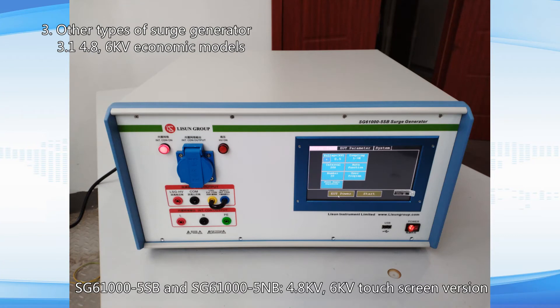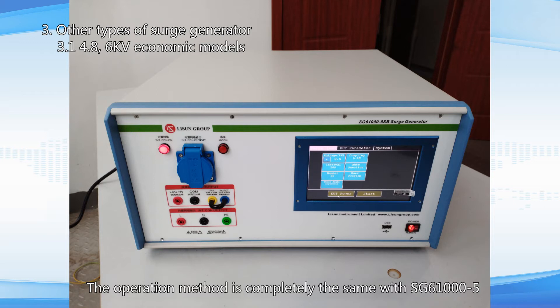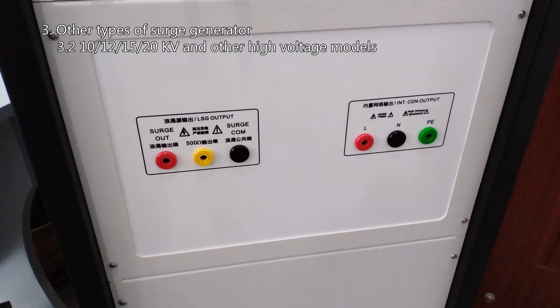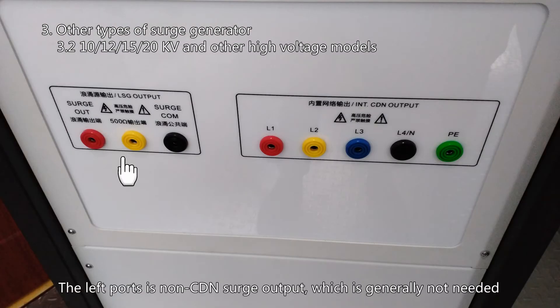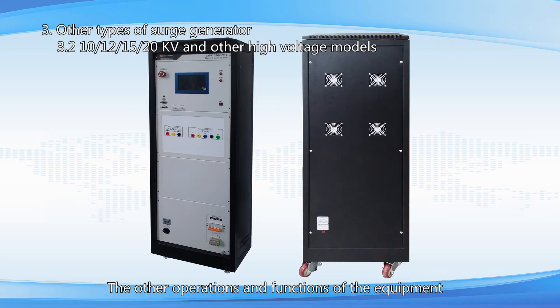The SG61000-5SB and SG61000-5NB have no oscilloscope interface, and the operation method is completely the same as SG61000-5. The SG61000-5H includes high voltage models at 10KV, 12KV, 15KV, 20KV, 30KV and so on. Depending on the object under test, the built-in CDN can be single phase or three phase. The left ports are non-CDN surge output, which is generally not needed. The safety earthing switch on the back needs to be always on. All other operations and functions are exactly the same as SG61000-5.